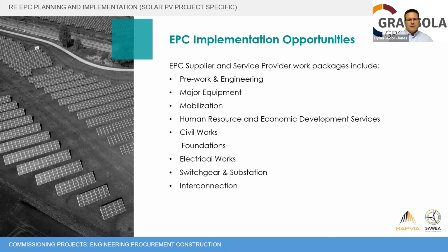And then naturally the communication cables also fall within that work package. The switchgear, substation, and interconnection typically go to a single contractor who specializes in switching stations. That would involve the supply of the transformers, switchgears, sometimes capacitor banks if applicable, and then obviously the transmission lines that feed into the interconnection point.